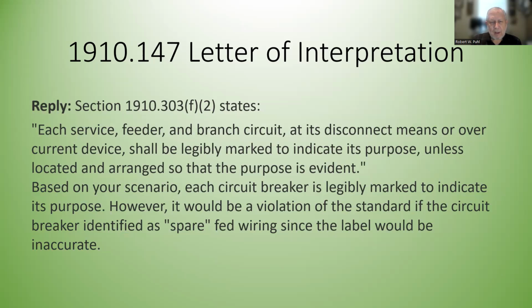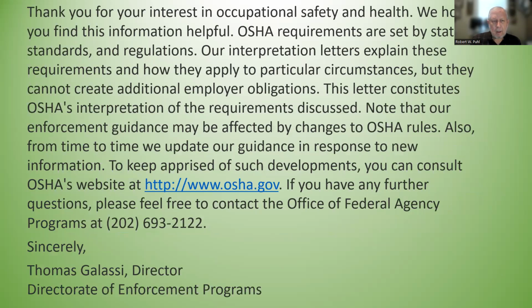Well, 1910.303(f)(2) states each service, feeder, and branch circuit at its disconnect means or overcurrent device shall be legibly marked to indicate its purpose unless located and arranged so that the purpose is evident. Based on your scenario, each circuit breaker is legibly marked to indicate its purpose. However, it would be a violation of the standard if the circuit breaker identified as a spare fed wiring, since the label would be inaccurate. So basically, what they're saying is that's okay because it's marked properly. If it wasn't, it wouldn't be. And then they're going to say, thank you for doing all this stuff.